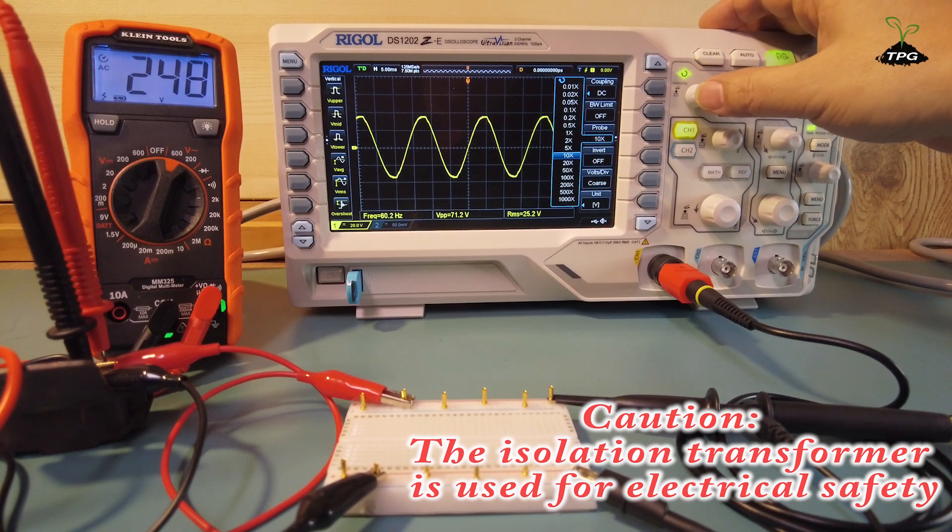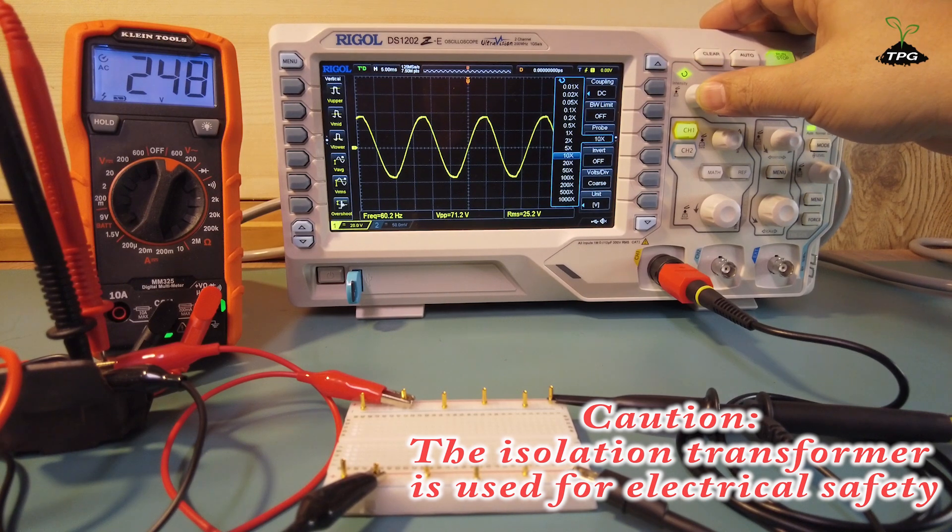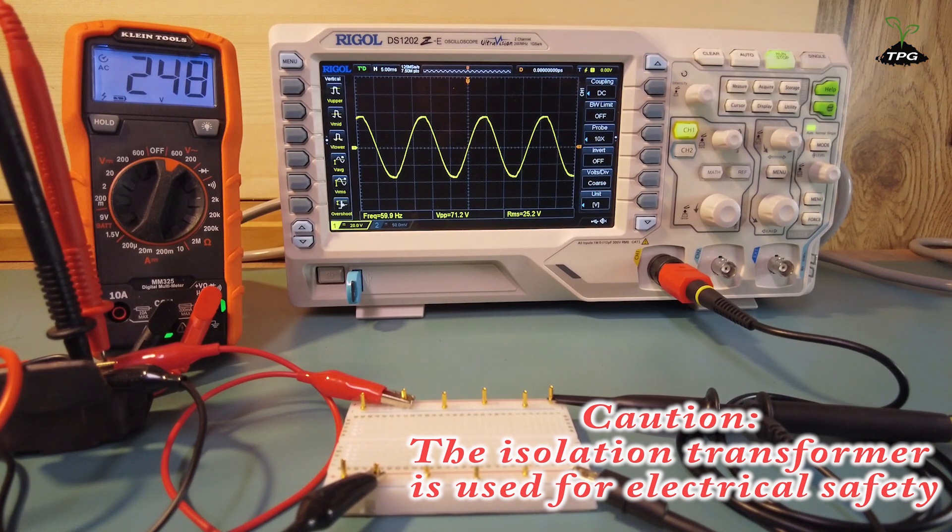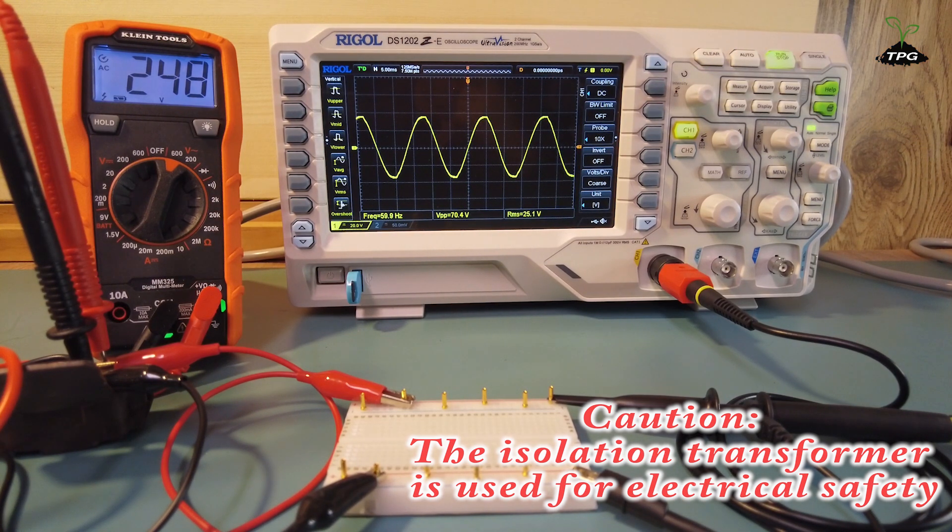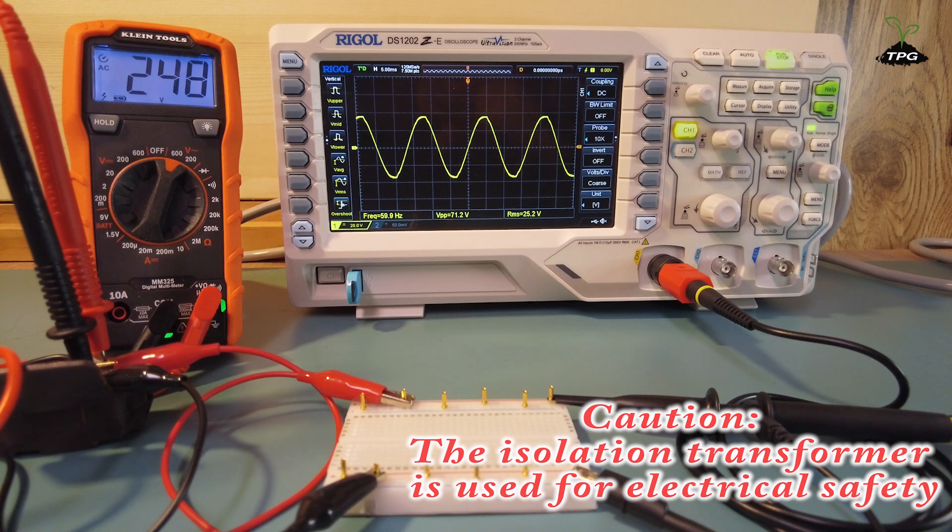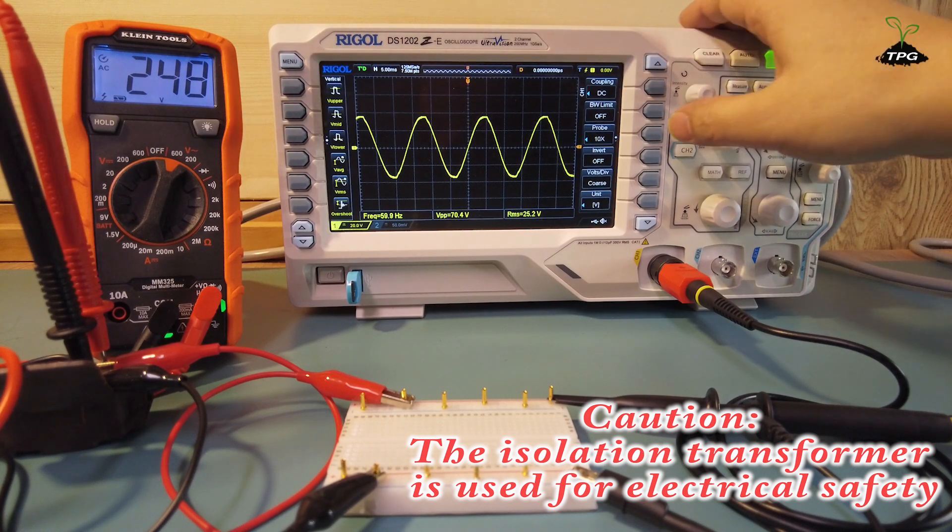Please note that, depending on the signal amplitude, using an incorrect attenuation ratio may damage the oscilloscope.